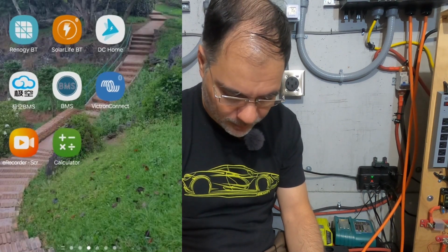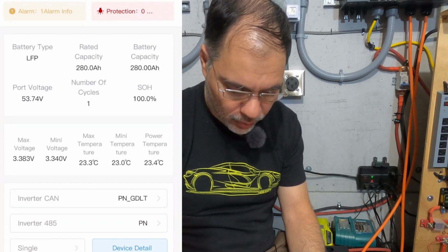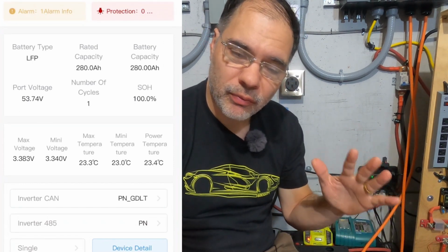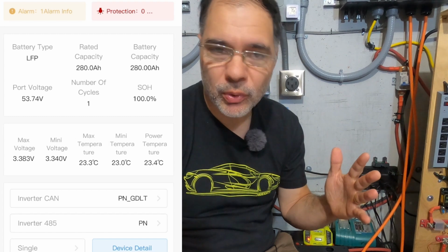So that's pretty good. It couldn't go all the way because once the cells drop below 3.40, the balancer stops working on them. So when it's charging on the charge balance, I think my charger is just pushing too much current. So we're going to try again to get to 54.4, or 3.40 volts per cell, and then we'll check the delta. If it's good, we'll try to push it up to 55.2.